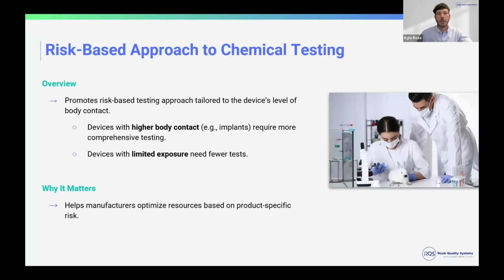The FDA also encourages a risk-based approach to this chemical testing. So make sure that the amount of testing is tailored to the device's risk level. So within that scope, we have how long the device is in contact with the body and where specifically it's in contact, as well as the risk of the materials that are being used, right? If it's a known material that's been used in implants with no history of any issues, then it's going to have probably a lower need for this chemical analysis.